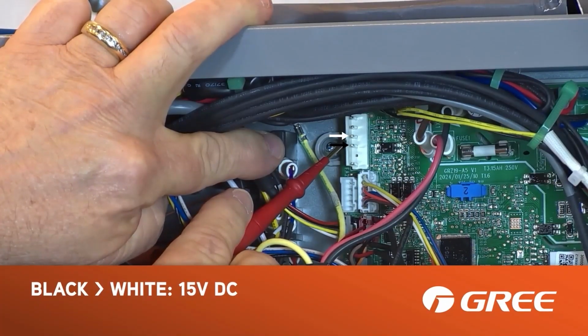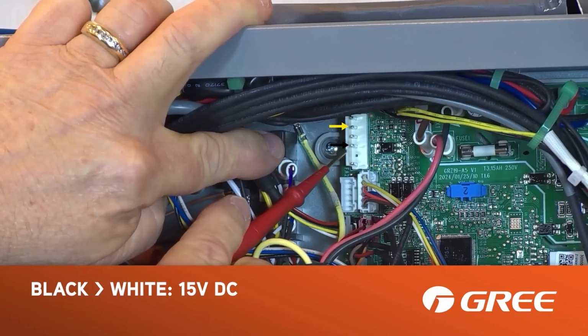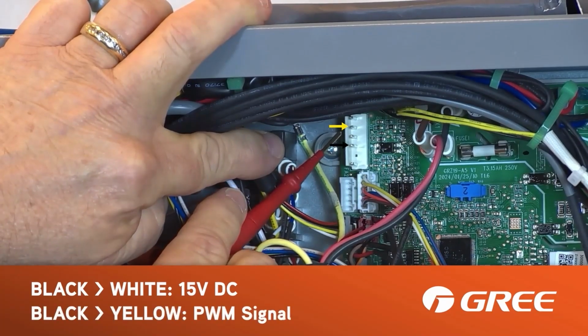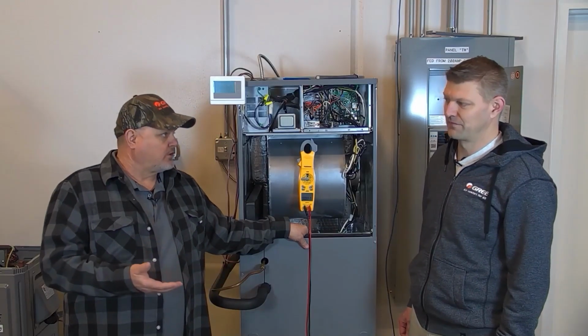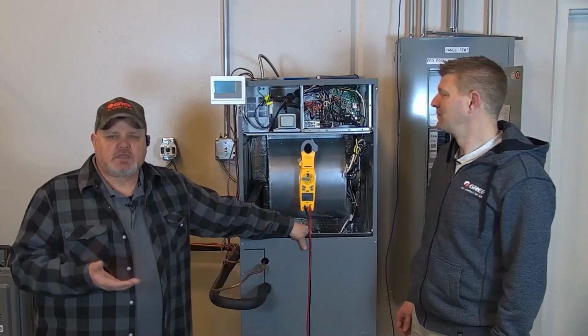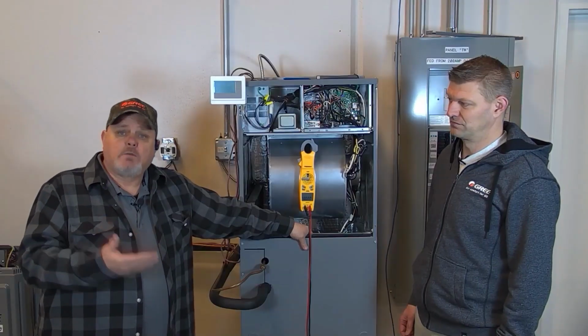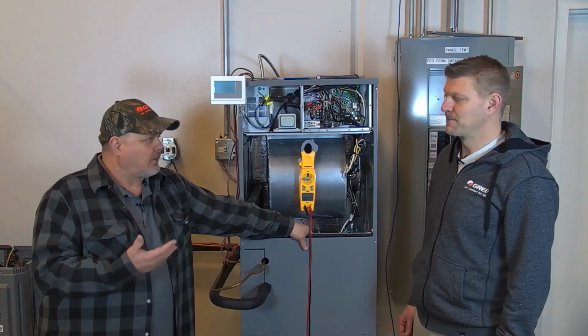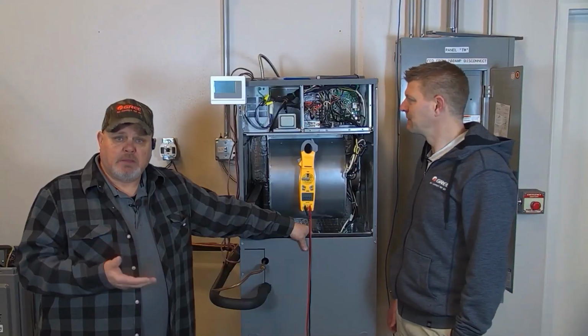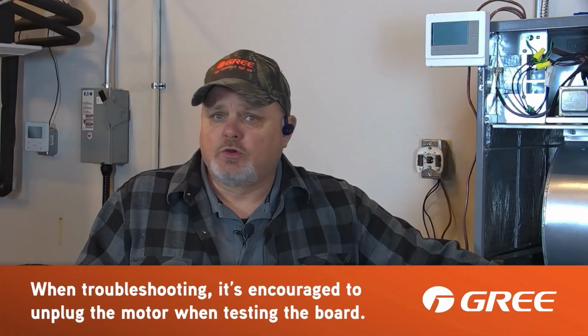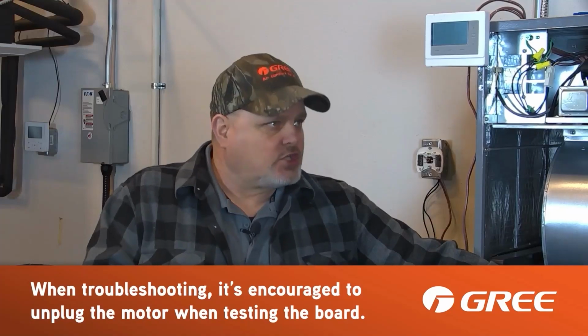That should give us 15 volts DC, and then black to yellow should show the PWM signal. If we get that, we know the board is good, and with the motor plugged up, if the motor won't come on, we know the motor is bad as long as the board is functioning. The unit we have has a working motor, so the only way to demonstrate this is to unplug the motor so it can't run. We're doing it on the pins, but I encourage you to do it with the motor unplugged to test just the board.